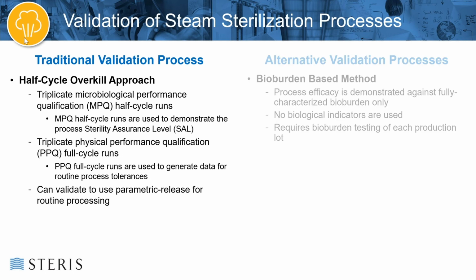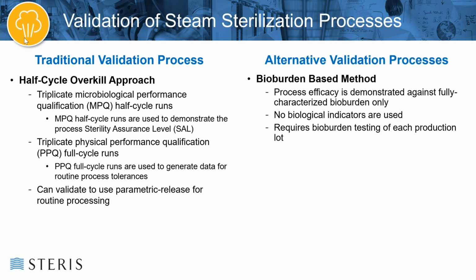Now, there are a couple of alternative approaches to process validation that are identified in ISO 17665-1. So there's the bioburden-based method, which demonstrates process efficacy against a fully characterized biome or bioburden of the materials being processed. So there are actually no biological indicators used during this validation approach. You're basing the efficacy of the process on the known and fully characterized bioburden on the devices prior to sterilization. One of the drawbacks of this method is that it requires intensive bioburden testing of each production lot. You have to make sure that what you're putting into the chamber does not present a greater bioload or a greater challenge to sterilization than what was validated using this bioburden-based method.